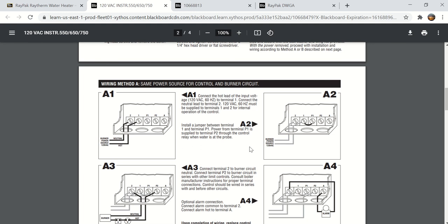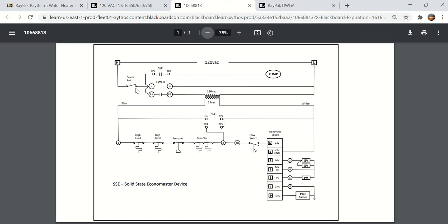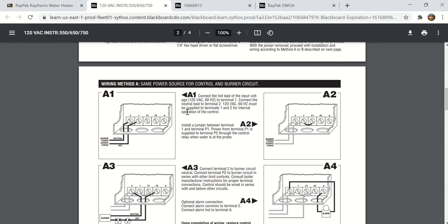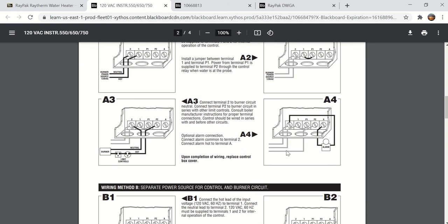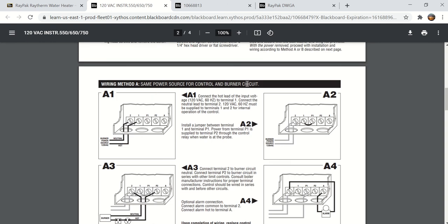So this is something I want to put on the quiz. I'll probably ask a question about the wiring method, because here it shows wiring method A, same power source for control and burner circuit. And when you look at our drawing here, you'll see that the same power that comes to H feeds down to P1, and that's what they're getting at here. The same power that comes to terminal 1 here, which is the hot terminal, also goes to P1. There's the jumper right there. So basically you're only using 3 wires. You've got your neutral, your hot, and then hot jumpers over to P1. P2 comes back, and on our drawing, P2 goes to the 120 volt side of the transformer that gives us our 24 volt circuit. So that is the method for using the same power source for the control and burner circuit.